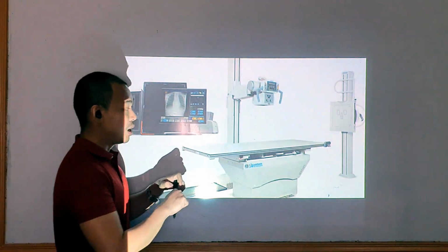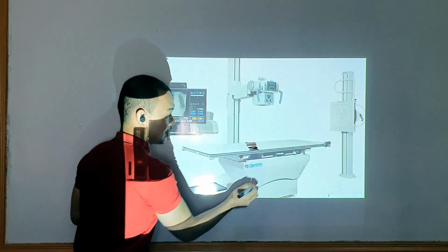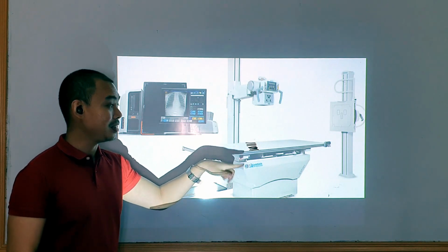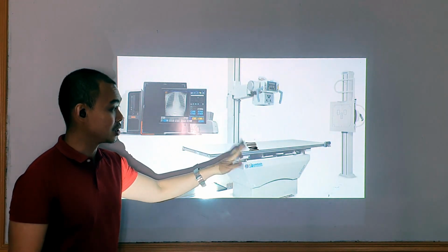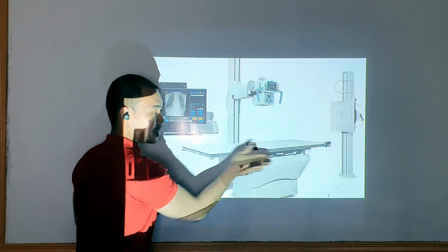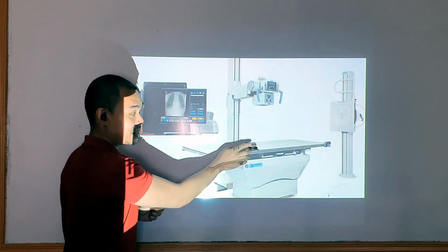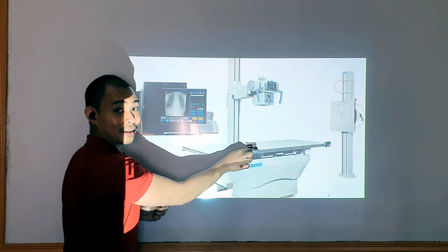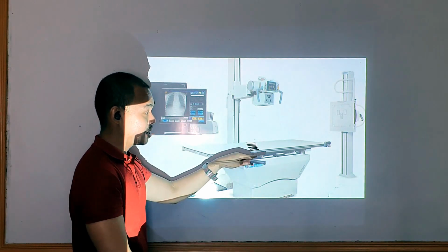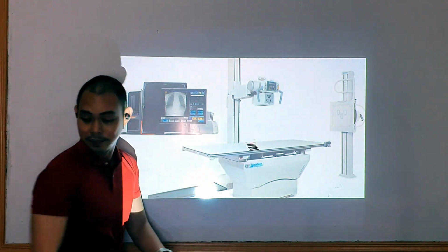It runs along the long axis. So you have your lead strips here. And it needs to blur the grid lines. It needs to move at the right angle. So what do you think should be the movement here? Is it like this or like this? It's like this because that's the right angle here, right? The lead strips run along the long axis. So obviously the right angle of this one is going to be back and forth, back and forth.